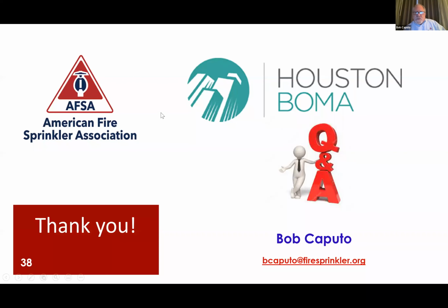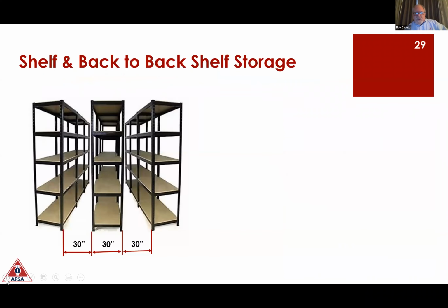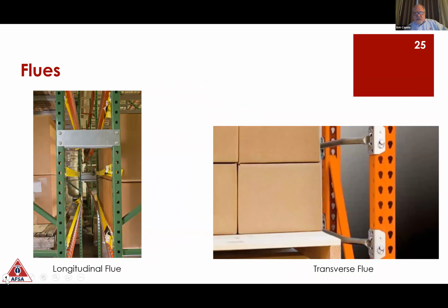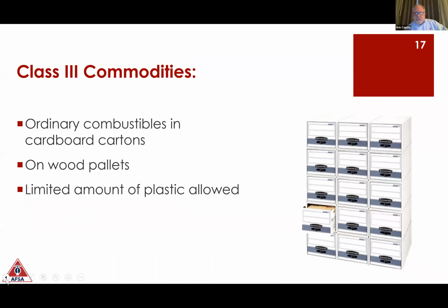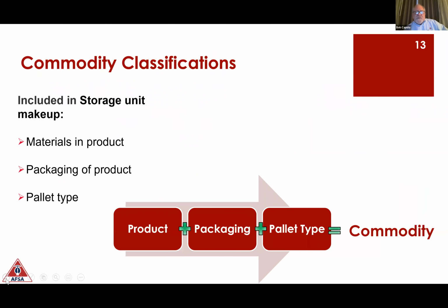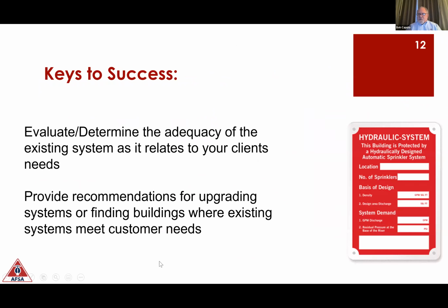So I went through all of those slides in as big a hurry as I could so that I could leave this remaining 20 minutes for as many questions as you might have and want to talk about. But I want to overemphasize the most important thing you need to know about these fire sprinkler systems. Most of the warehouses, especially around big cities like Houston, are spec lease buildings. They aren't built for a specific tenant where we've looked at the fire sprinkler system and designed it based on their exact need. Rather, we're looking at what you guys call flex space, what we on the West Coast call speculative lease. So we have to match the tenant to the building based on the fire sprinkler system, or we have to evaluate the fire sprinkler system for adequacy based on the client need.